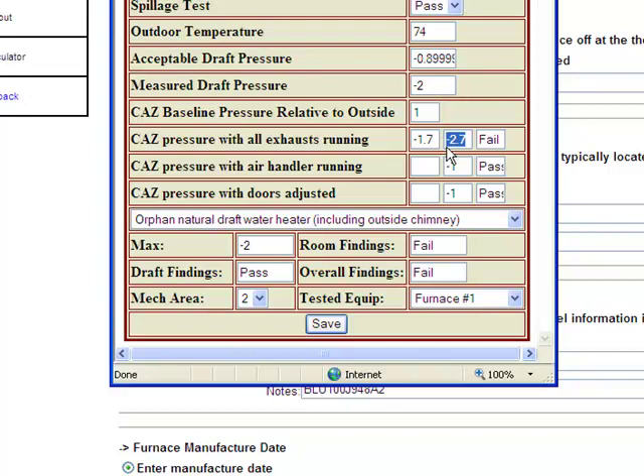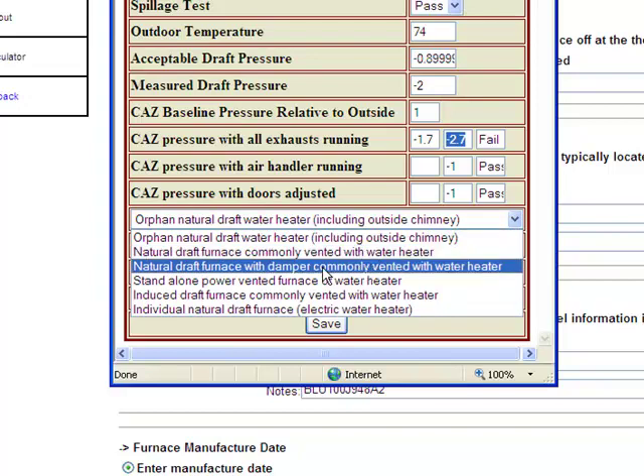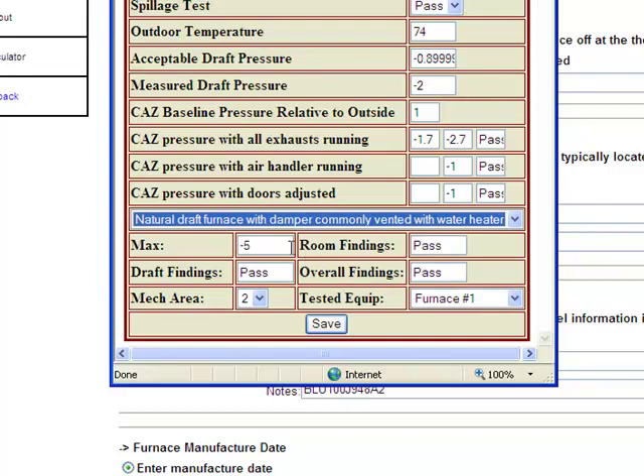Not only is the calculator computing the difference between the baseline pressure and the pressure in the different scenarios, but it's already telling you whether or not that passes or fails based on the maximum negative pressure allowed in the CAZ — determined by the combustion appliances in that zone and how they are structured relative to each other. For instance, with an orphan natural draft water heater the threshold is different than with a natural draft furnace with a damper, commonly vented with a water heater, where you can go to a negative 5 pascals — so the CAZ pressure would now be passing.